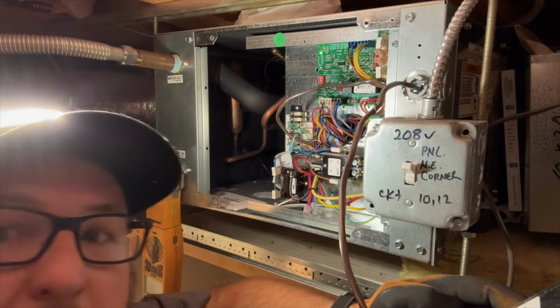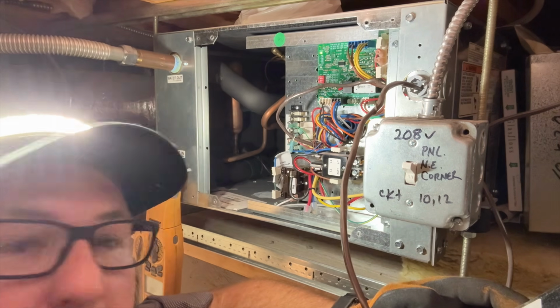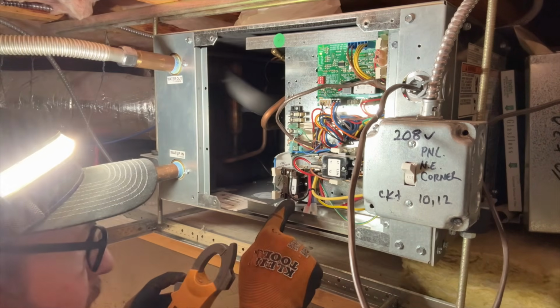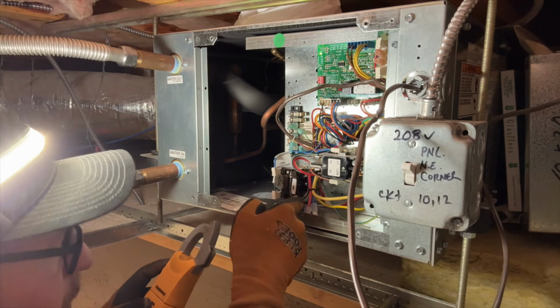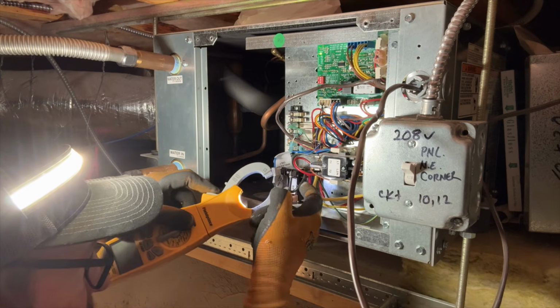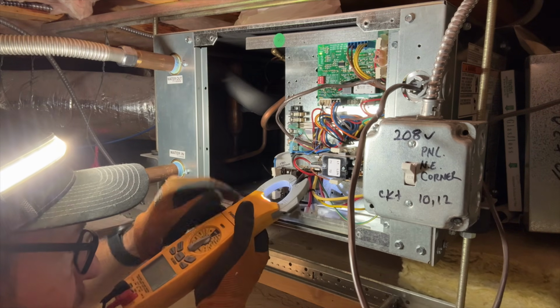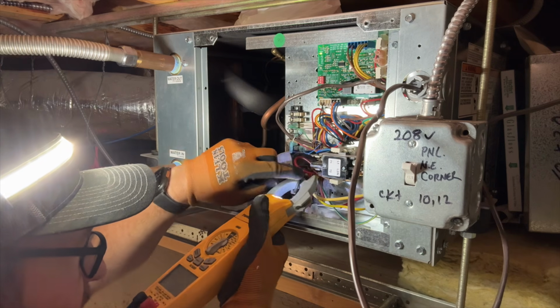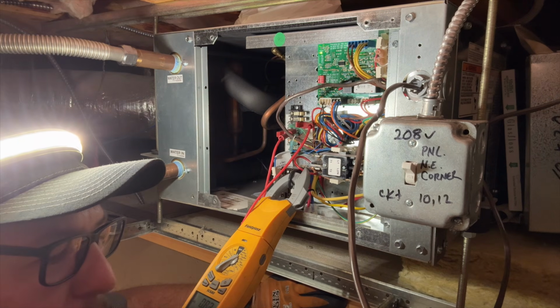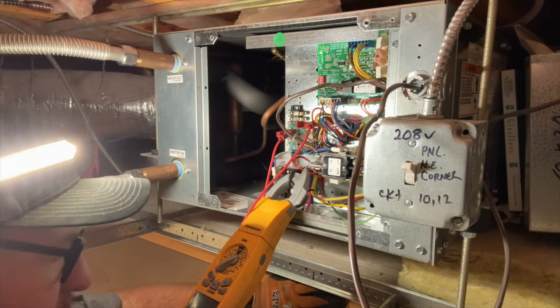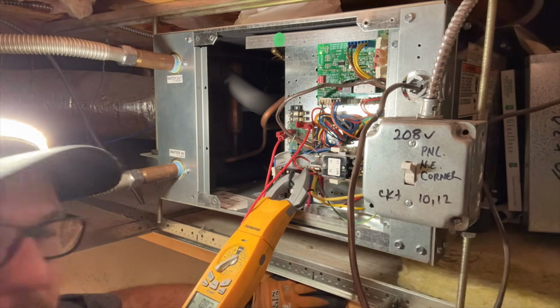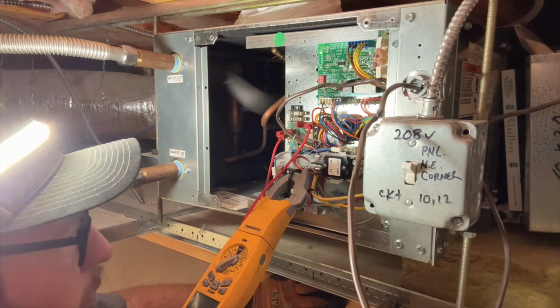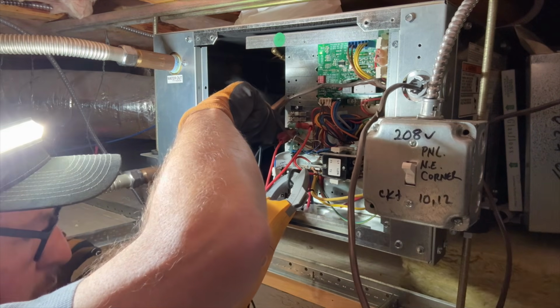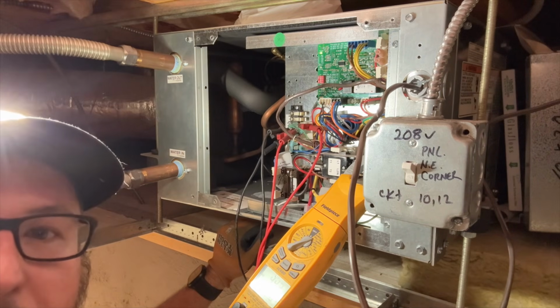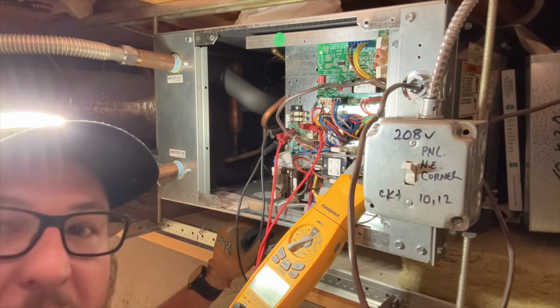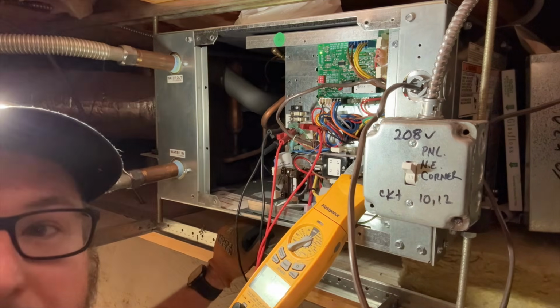So let's go ahead and start cycling this thing and we'll see what it's doing. Okay, so this relay right here, this is the fan relay. This is going to the blower motor. Looks like it's set for high speed. I'm gonna get my amp clamp on there. We're gonna start with the fan motor, make sure that's not the cause. Okay, so the full load amps on the blower motor is 0.96 amps. I'm getting 0.82, 0.83-ish. It seems to be normal. Okay, so our total amps for the entire system is at 4.5 amps.